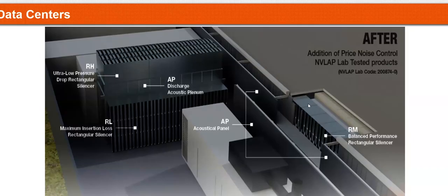In this specific case, even though it looks simplistic, there is a massive acoustical barrier catwalk so that the sound from the generator gets blocked by the barrier, but also what goes over can get absorbed within the catwalk and then by the silencers. All those air handling units pulling air in to condition those servers also have sound power, and they just don't have one silencer. Every set of louvers here has one of those big units. So an entire array of about 50 silencer banks per side is what you could see behind this wall.